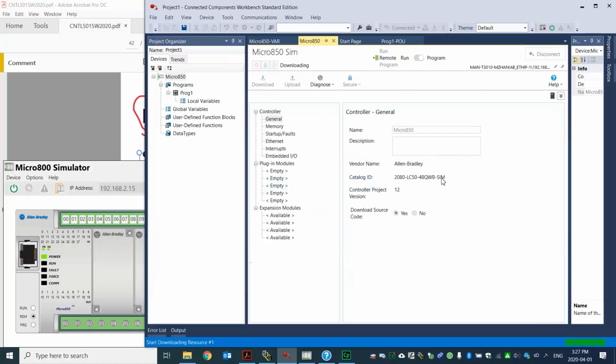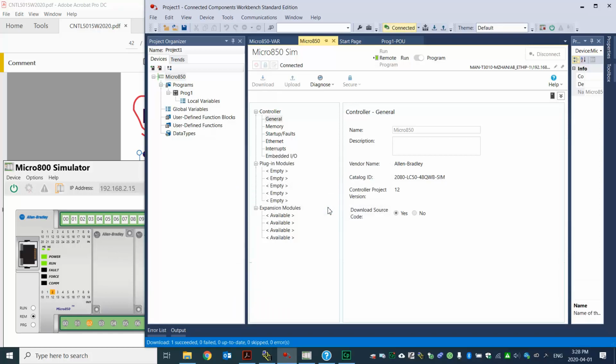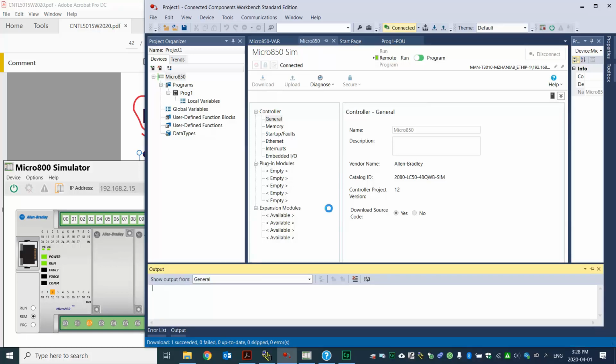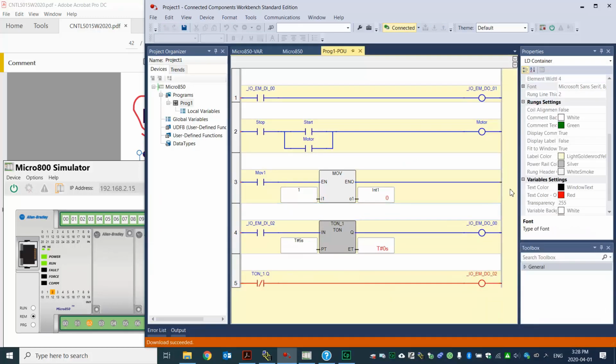So TON, remember that we talked about on delay, can provide two different types of timed output: normally open, time close; normally close, time open. Right? So basically, I program my logic according to these two outputs. So the 0, 0 will have the normally open, time close. 0, 2 will have the normally closed, time open.